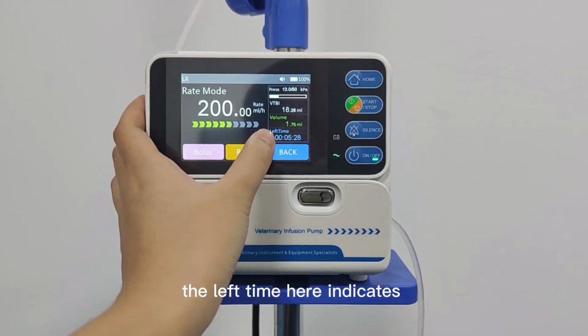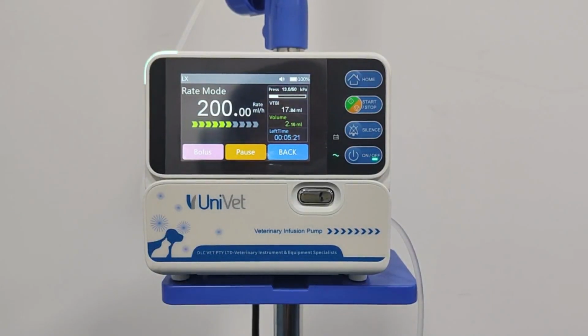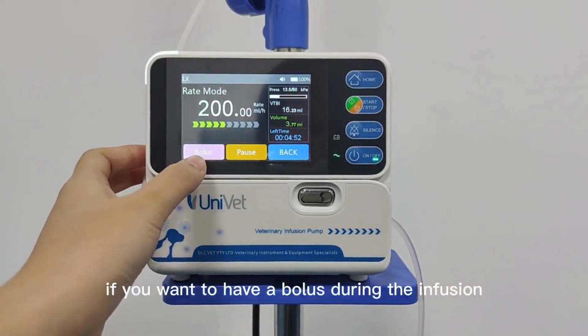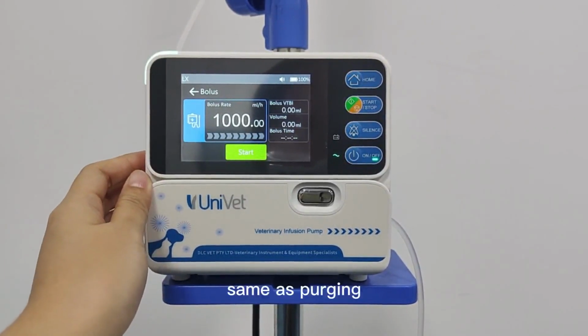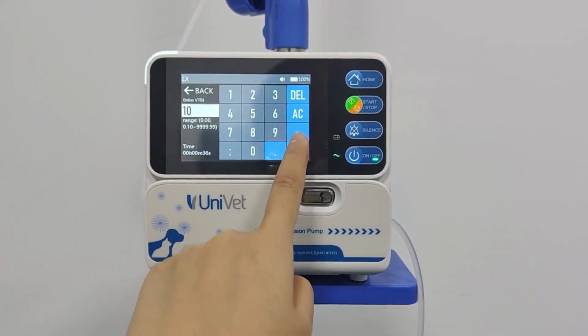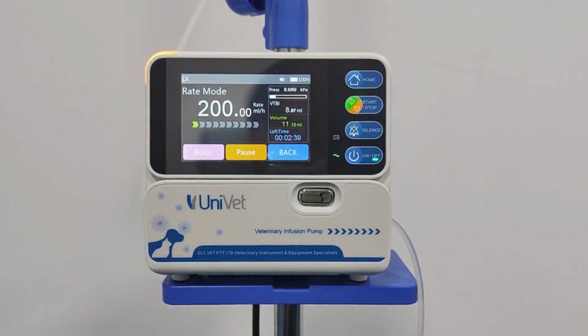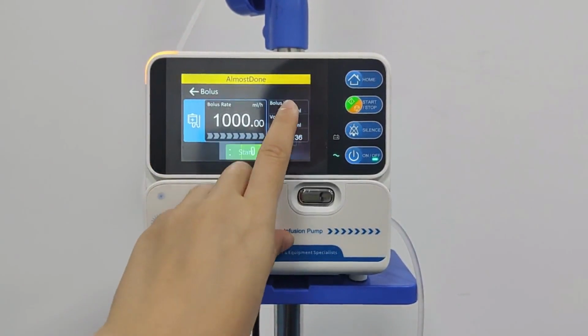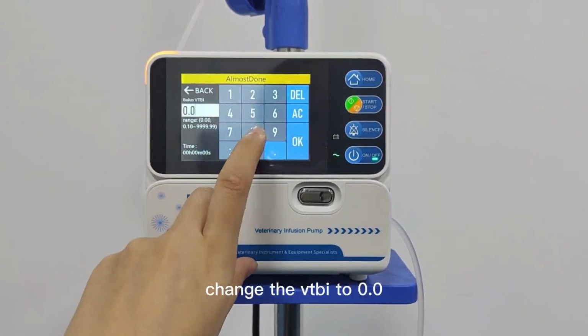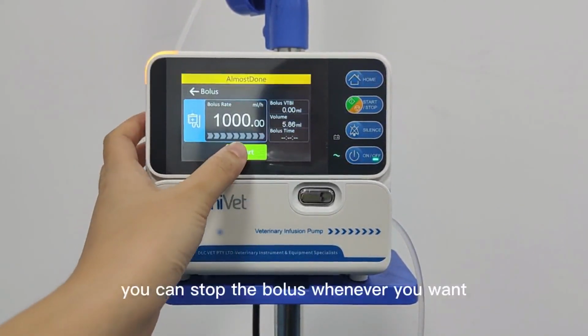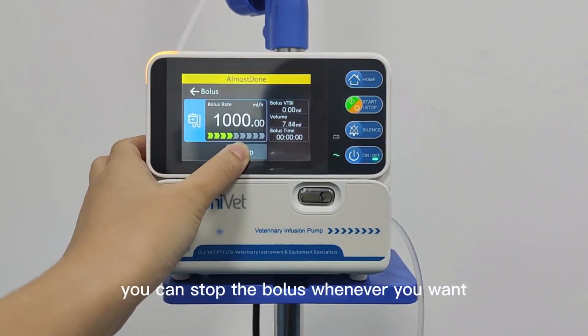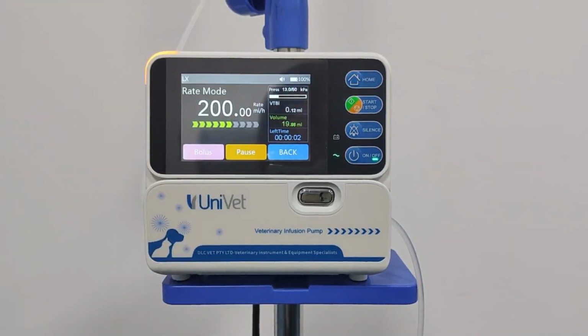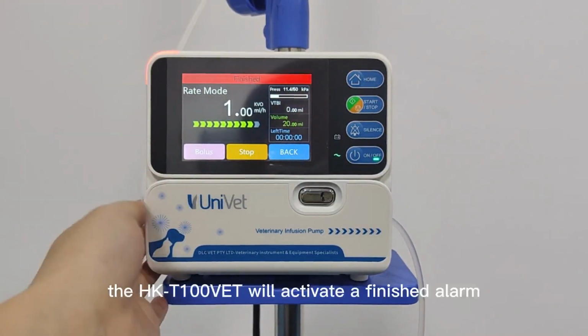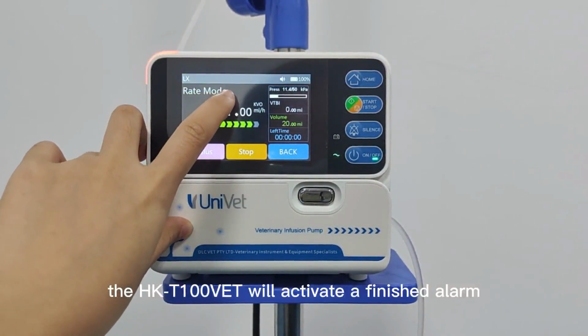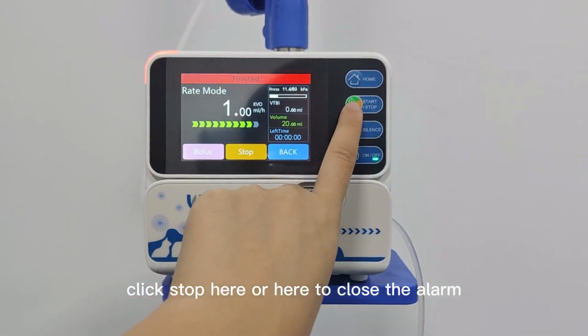The left time here indicates how long before the infusion ends. If you want to have a bolus during the infusion, you can click bolus. Same as purging, if you input the VTBI, it will be an auto bolus. If you want to have a manual bolus, change the VTBI to 0.0. It means manual bolus. You can stop the bolus whenever you want. When the infusion is finished, the HKT100VET will activate a finish alarm. Click stop here or here to close the alarm.